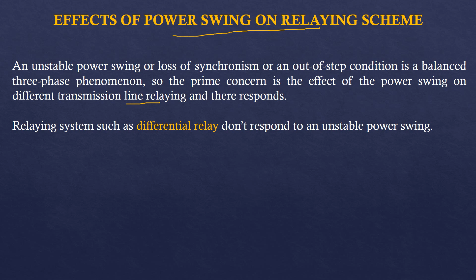Whereas talking about the distance relay, overcurrent relay and the directional relays, these relays are greatly influenced by the loss of synchronism or out of step condition of the generator and therefore they respond to the unstable power swing. And while responding to the unstable power swing, they can maloperate and can trip the circuit breaker associated with them. Therefore, a specific topic regarding the effect of power swing on distance relay will be discussed later on, as to how the distance relay gets affected as a result of unstable power swing.